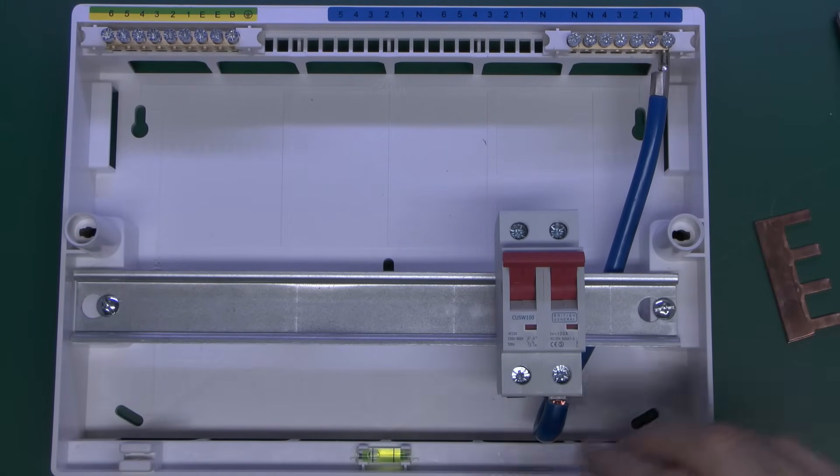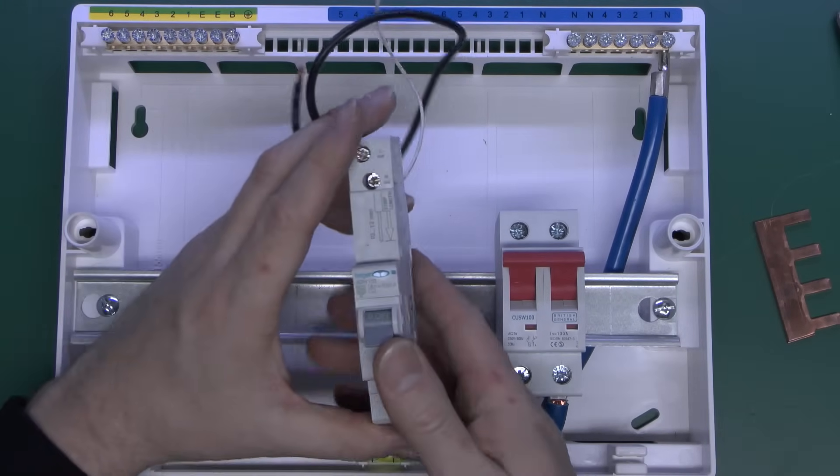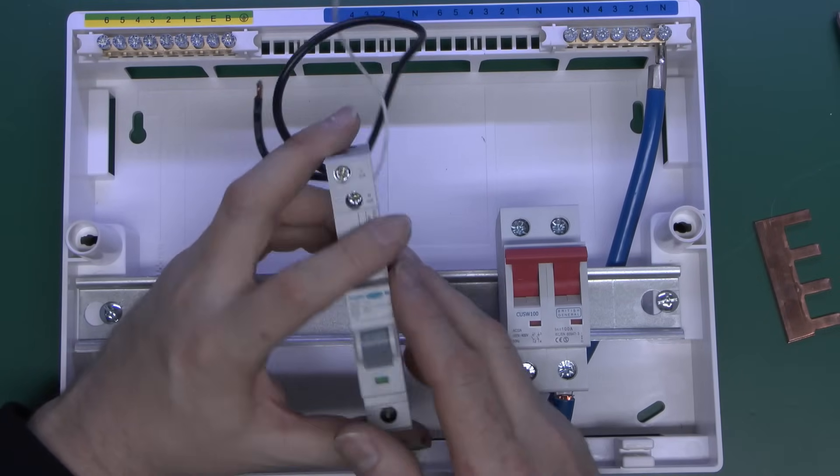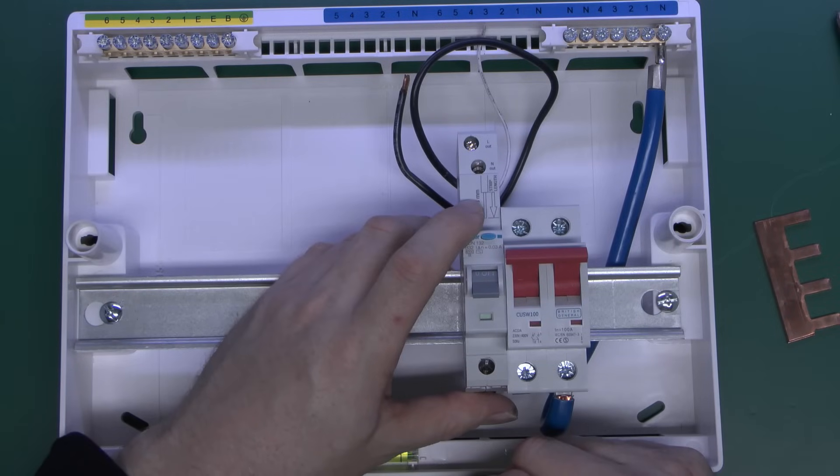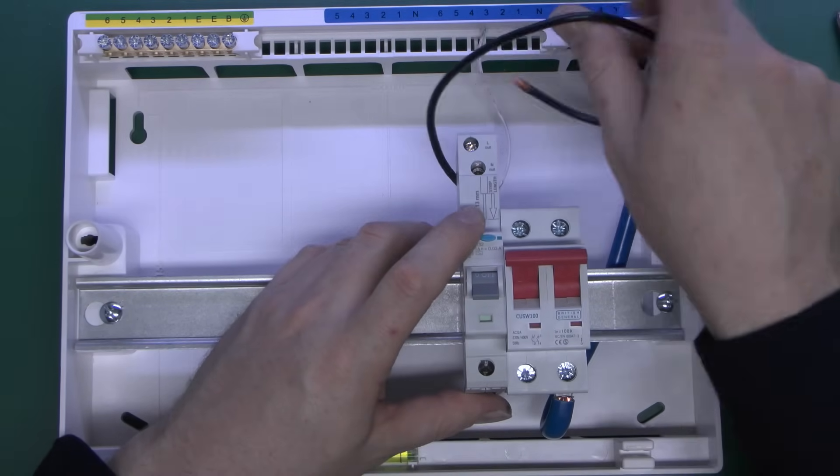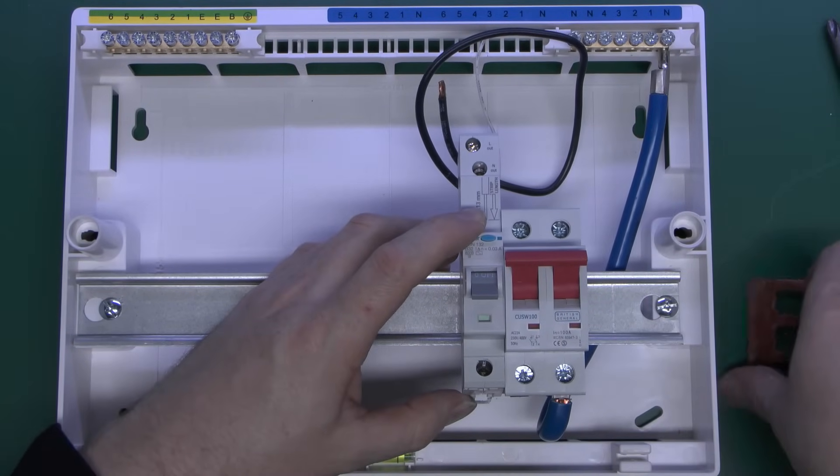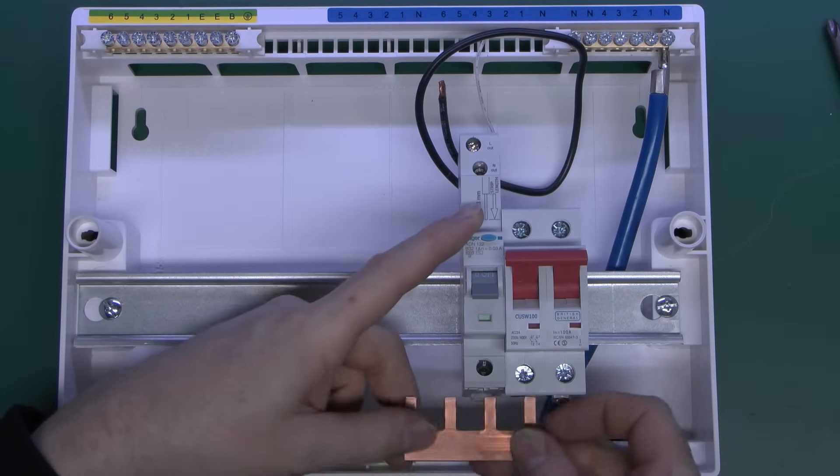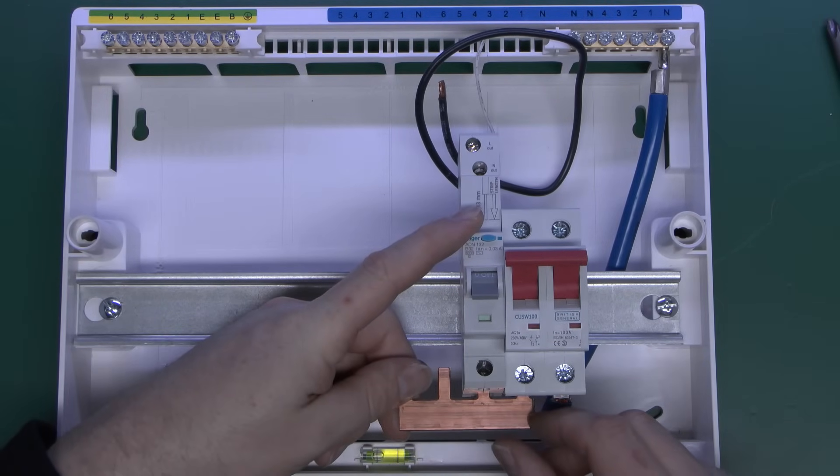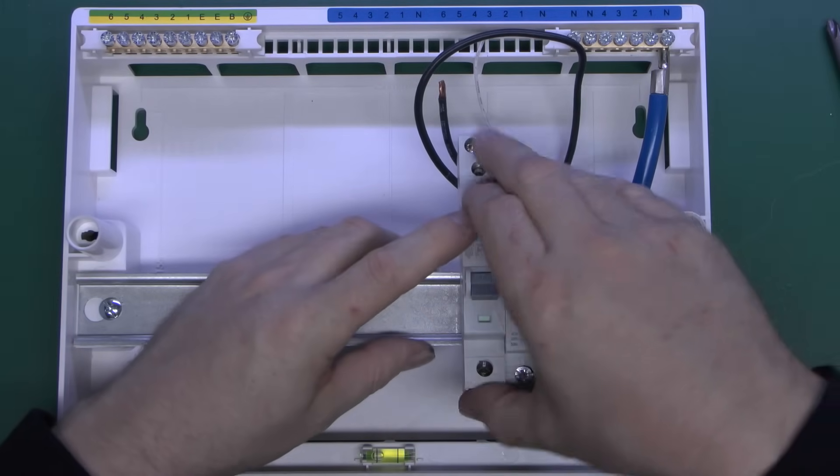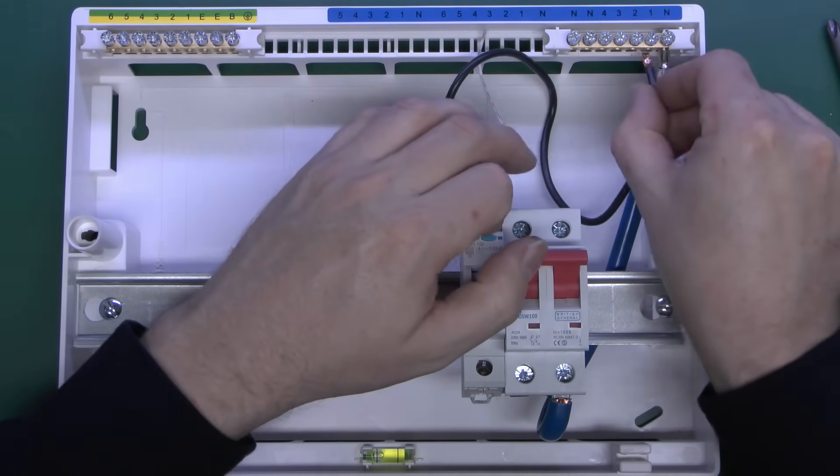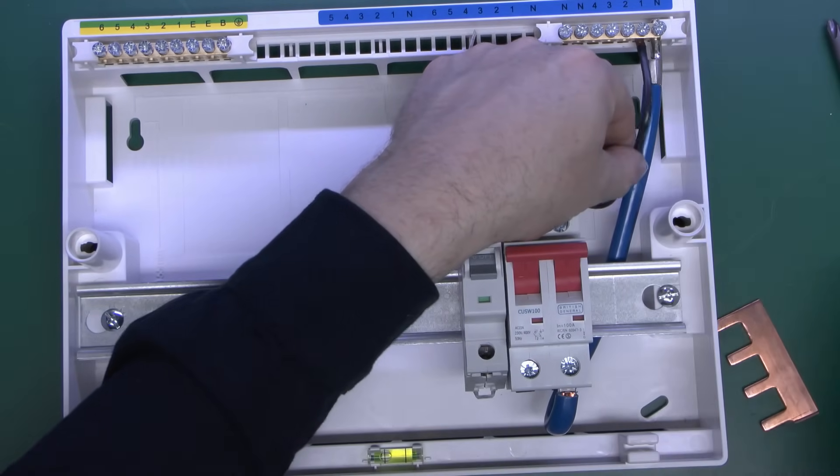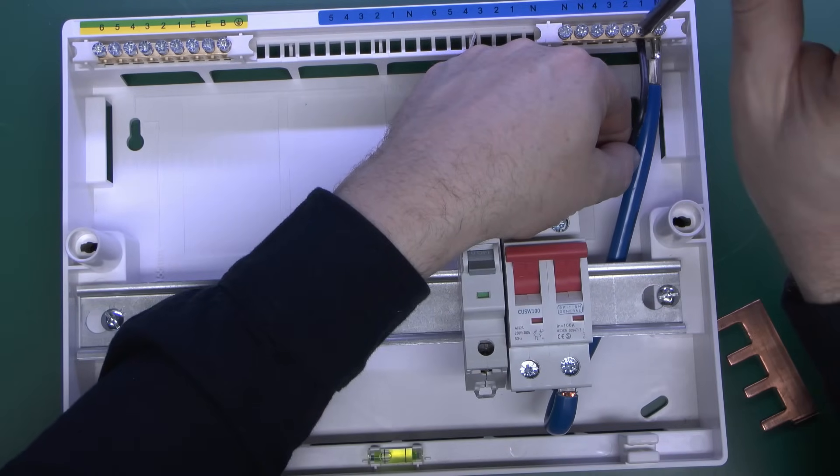However in the case of the RCBO because this has the RCD functionality built in it needs to monitor both the line and the neutral so again it just fits onto the rail in the same fashion. But as well as the line bus bar connecting here in the bottom just in the same way as the other devices we've also actually got this additional lead here which is for the neutral so that is what connects to the top here in the neutral bar.